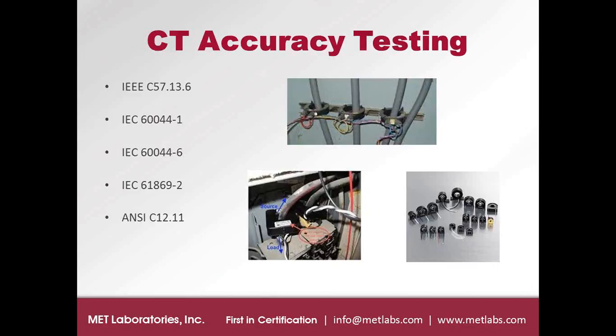The CT accuracy testing: the IEEE C57.13.6, IEC standards, as well as the ANSI C12.11, all primarily having to do with, our focus here really, the accuracy of those CTs. We can offer those types of programs as well.